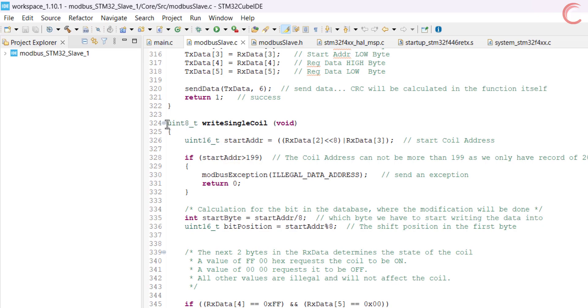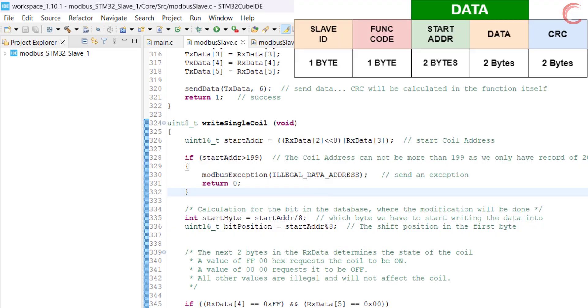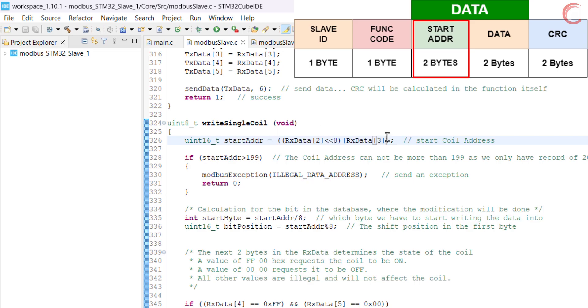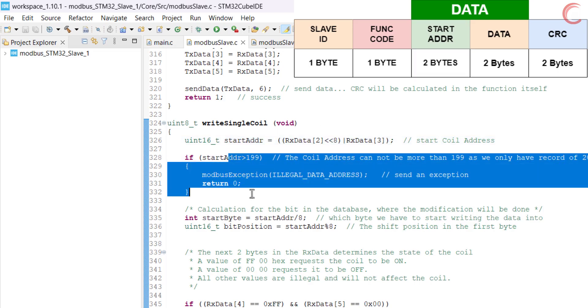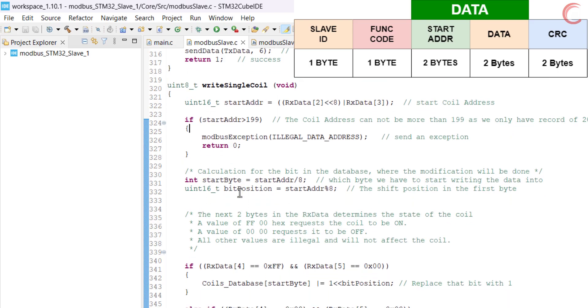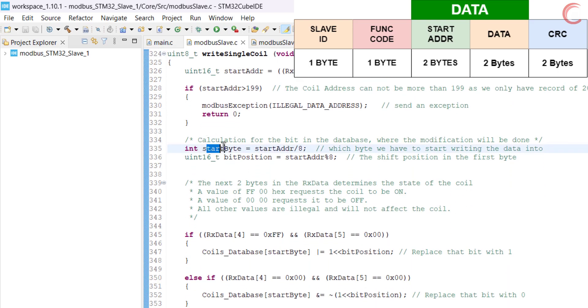Let's take a look at writing a single coil. Here first we will extract the address of the coil which the master wants to modify. If the address is greater than 199, the slave will send an exception, because the database is defined for only 200 coils. Next we will calculate the start byte — this is the byte in the database where the modification will be done.